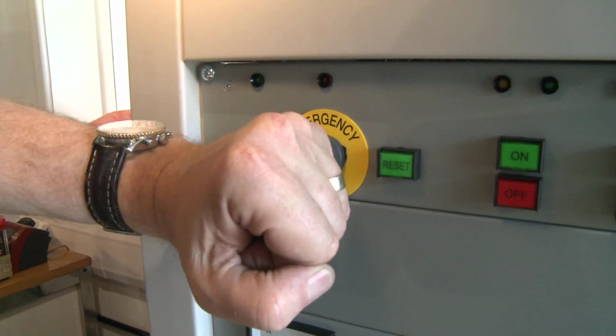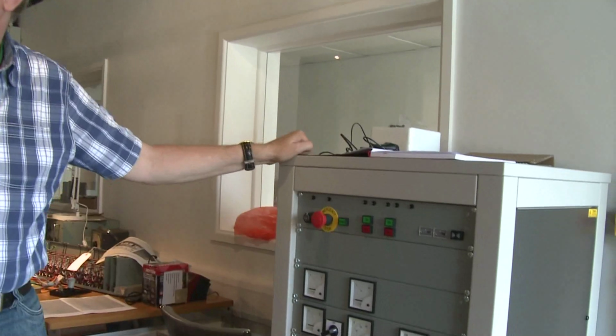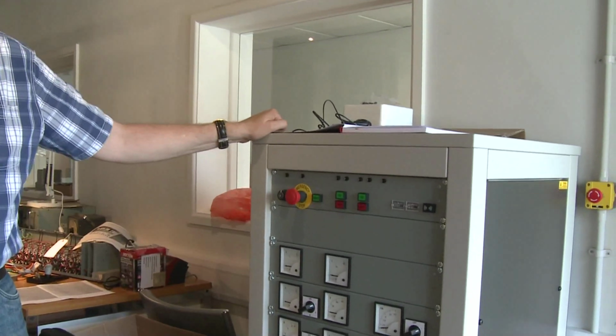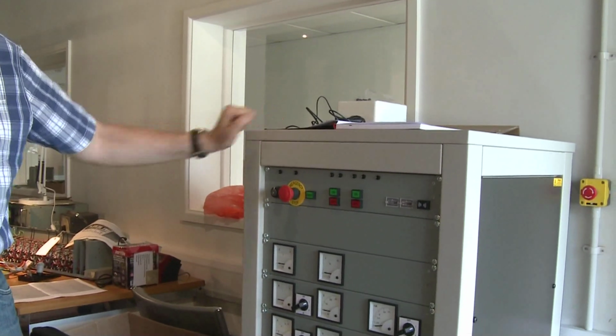Then the box automatically brings up the high tension, again in two stages, so that we're not subjecting the machine to wild swings in voltage, and we're only applying the high voltages when the machine is warm. There's also a big red emergency off button, and indeed there are buttons all around the machine area, so if there's a problem while we're working on it, we can instantly isolate it.